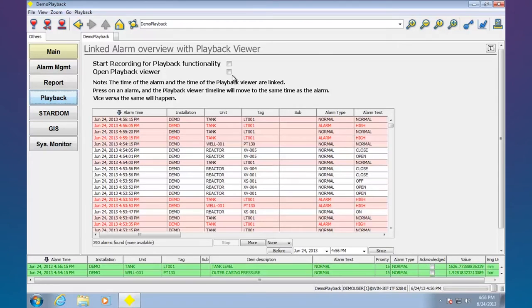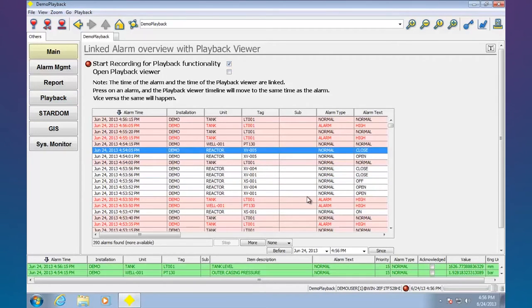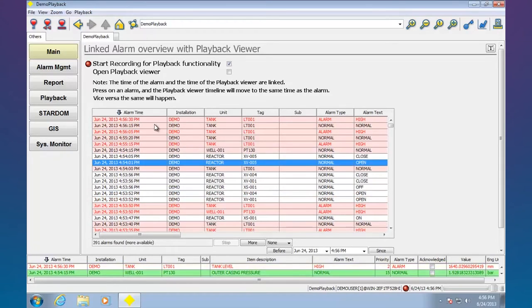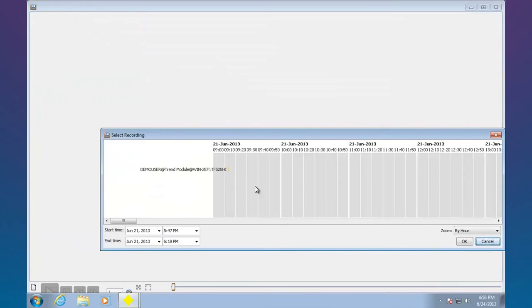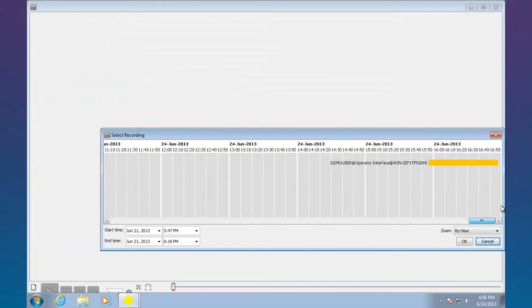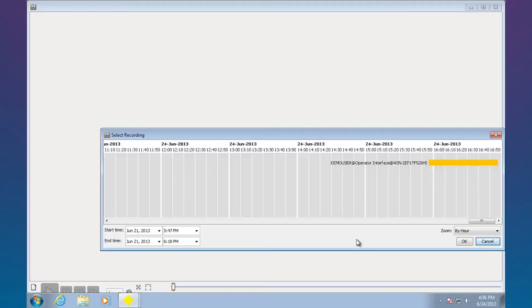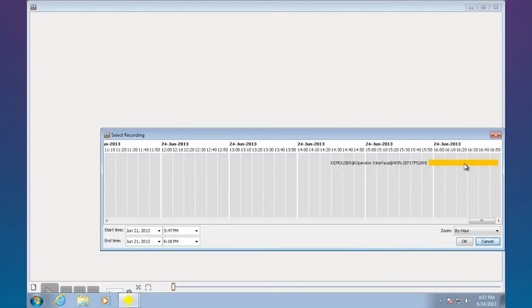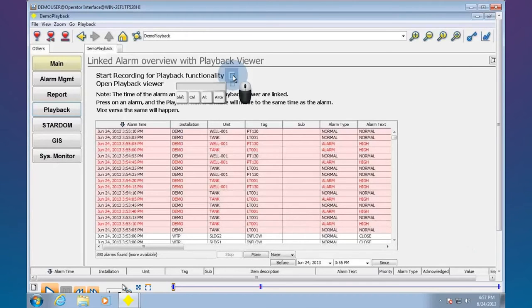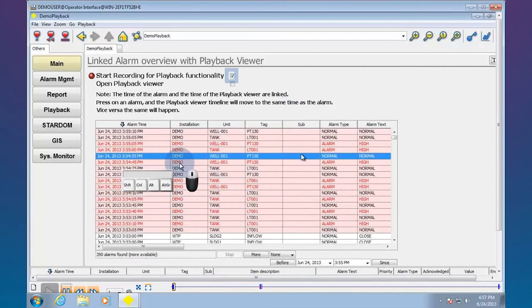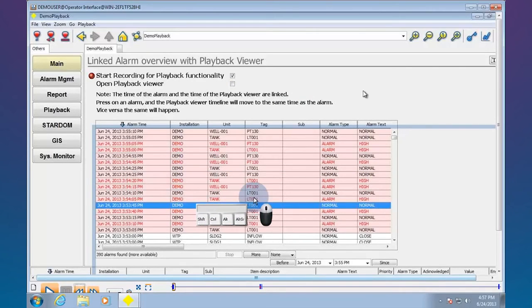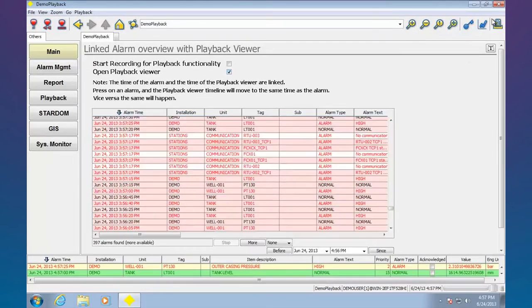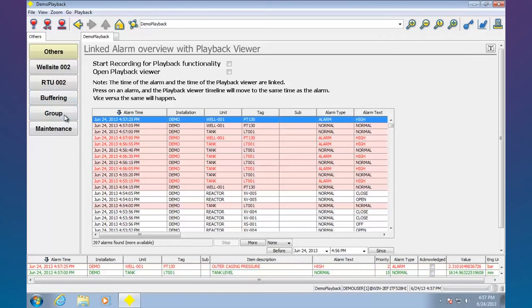I've got another neat capability here called playback. I can go ahead and record what's going on on the screen including mouse movements where I click. I can actually then do a playback on exactly what happened there. So maybe this is for training. Maybe it's for just operator education. Like say something happened out on a site and you wanted to know exactly what happened. If this recording was set and we set it to record every day and keep the most current days worth of clicking and keyboard actions in place, then you could always play it back to see exactly what happened during a certain event that happened during the day. So I can open that up, go down here to the VCR controls. We can see how the mouse moved around, what it clicked on on the screen. That's the playback option.